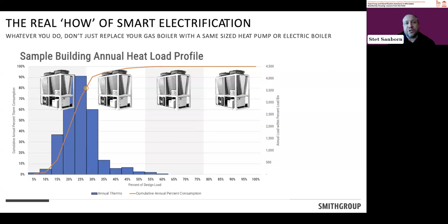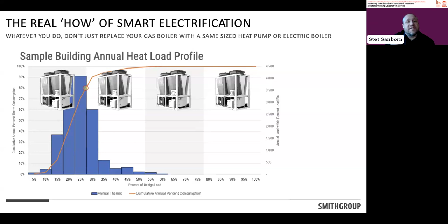And so my question to you is, well, how much heat pump capacity do you really need if your building isn't actually using that much heating? So to stress David's point, short of doing a Manual J calculation, I really, really, really encourage you to take time to go measure your building loads for the year. So if you're not sure when you're going to do your decarb plan, start planning now by collecting the data. Have an engineer come out and throw a BTU meter on if you don't have one, and track your building's use. Because I can guarantee you, if you're bumping up into cost barriers and electrical capacity issues, right-sizing the equipment is going to solve both of those.